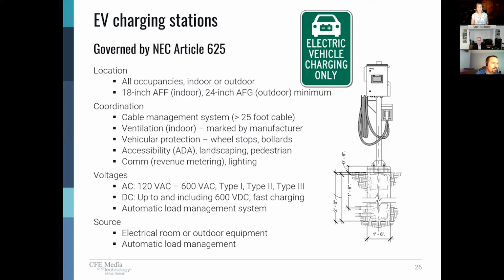And then type 3 is more of a commercial installation that's similar to a gas station fuel stop type of installation. And that standard is ongoing. It's in flux. As the technology evolves, we expect to see some changes there. So that one's still yet to be defined fully. And then on the DC side, which is typically reserved for fast charging, up to 600 volts DC, you typically see that in installations for shuttle buses or where you've got a metro busing system.